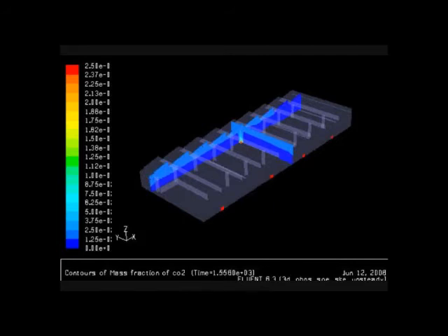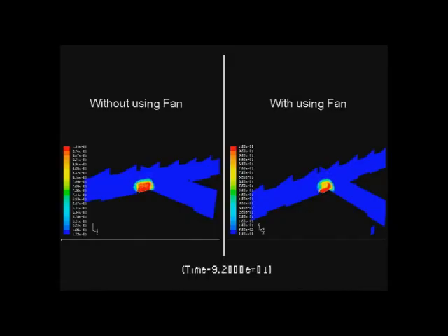The dense smoke is coming down slowly, and it came down to about human height in about 15 minutes in this case. The first ventilation system that we tried, obviously, was not good. Then we tried another system with roof extract fans, smoke-rated roof extract fans, and this was able to keep the smoke layer above human height for up to 1 hour, which was what the standard specified. We have to keep the smoke above human height for up to 1 hour from the initiation of the fire.